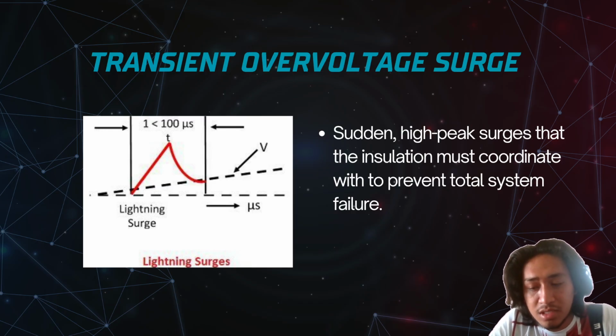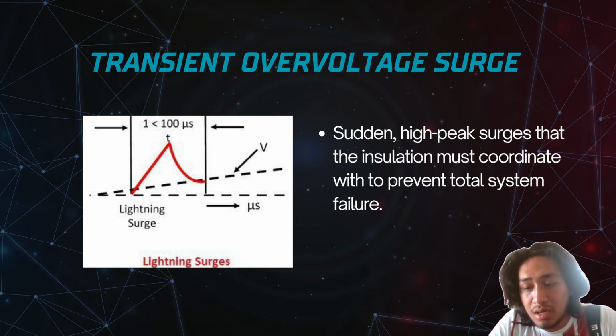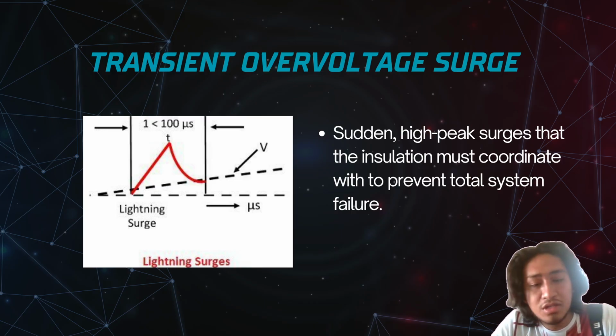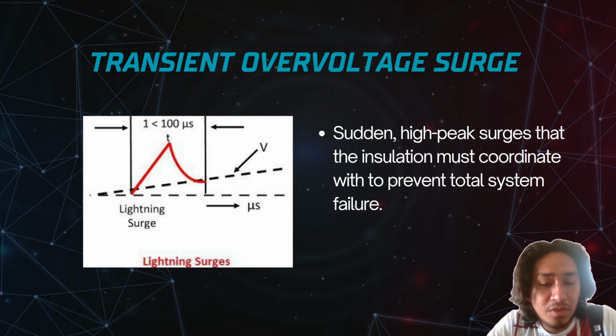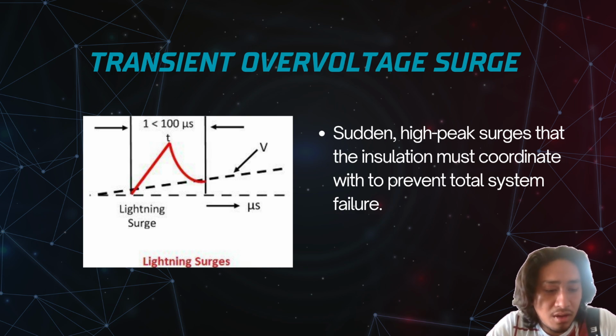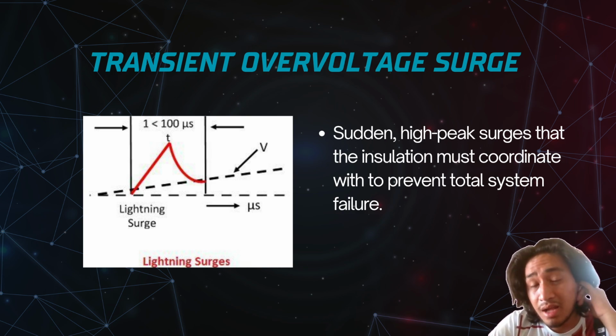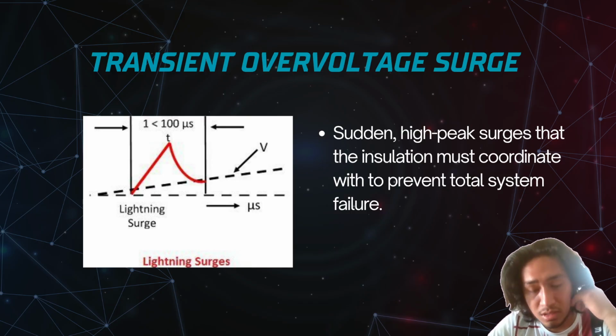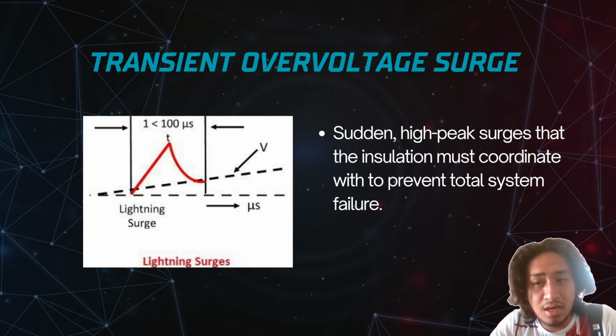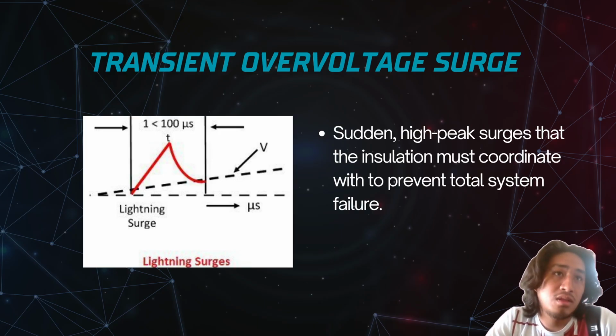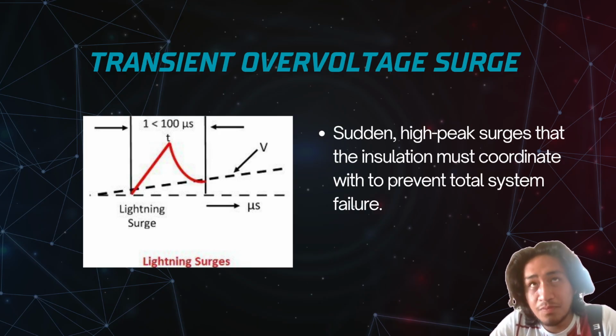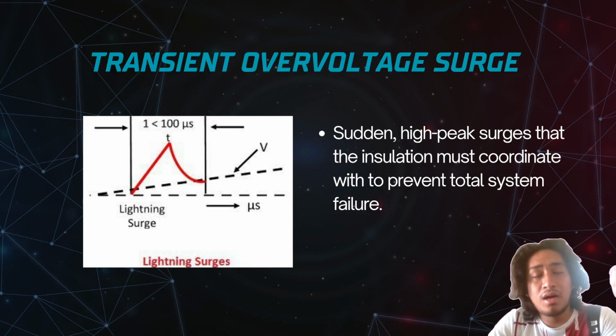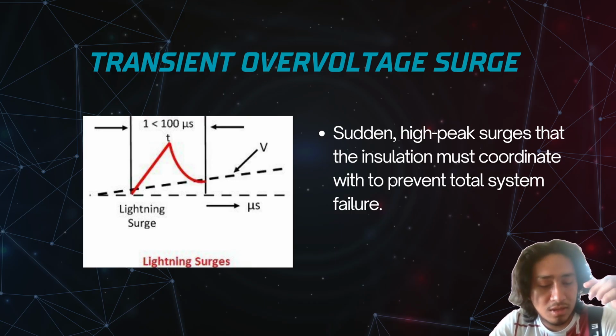So reading from the PPT: sudden high peak surges that the insulation must coordinate with to prevent total system failure. So this factor has a very short duration, however, but a very high voltage spike, exceeding up to 20 times the normal operating voltage. So this phenomenon occurs during lightning. During lightning, the lightning strikes our transmission tower.